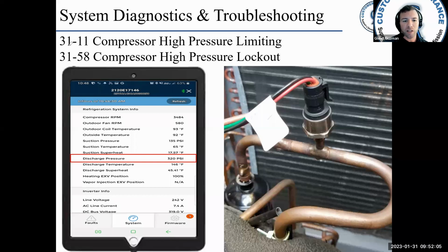So you get to 3111, okay, it ramps down. Let's say you're at 100%, you ramp down to 75, ramp down to 50, and you're down at 25%, which is the lowest. If you have to ramp down again, then you're going to go to 3158 and you're going to get the lockout. Okay. Visually inspect the equipment. Okay. What could cause high pressure in the system?